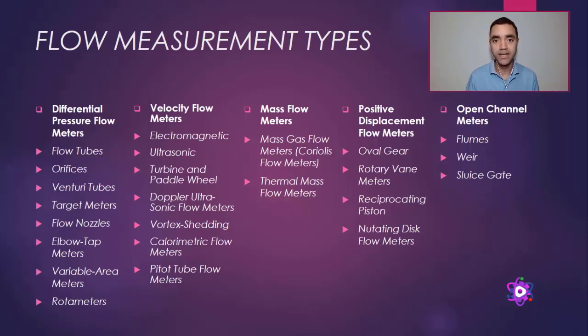We need to convert the actual volume flow that we have in the process into a standard volume flow, where we know the basis of pressure and temperature, to always have the same references for the process. That is especially important when we are talking about gases because they are compressible fluids, and a variation in pressure and temperature can vary the mass density of the fluid a lot, and that can give you totally different measurement numbers for the same mass flow that you have in your process.